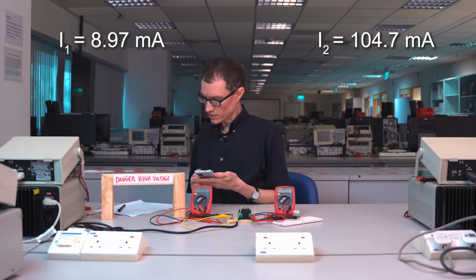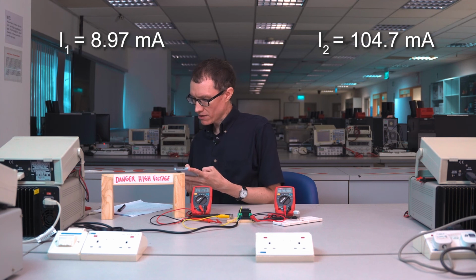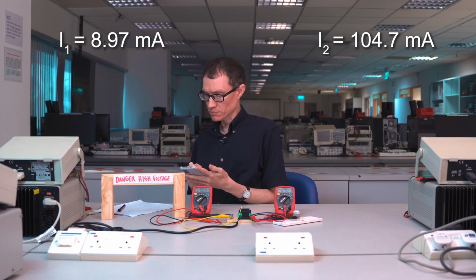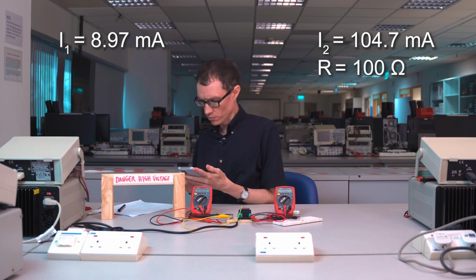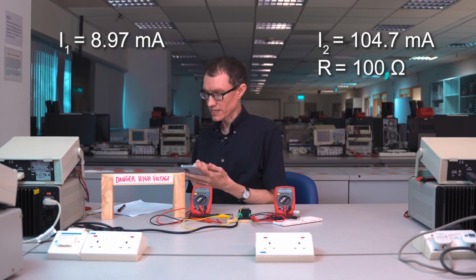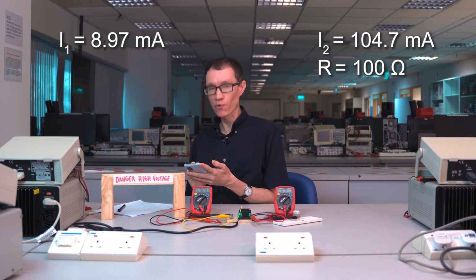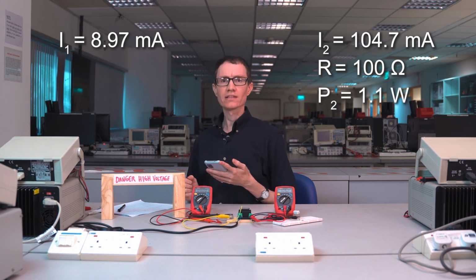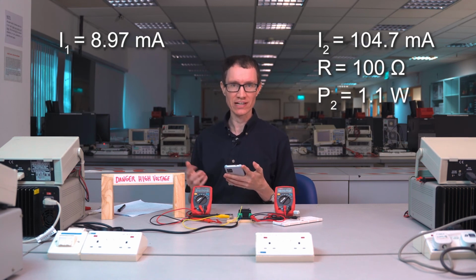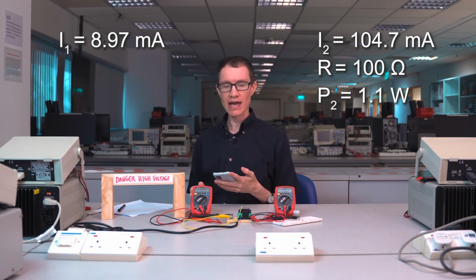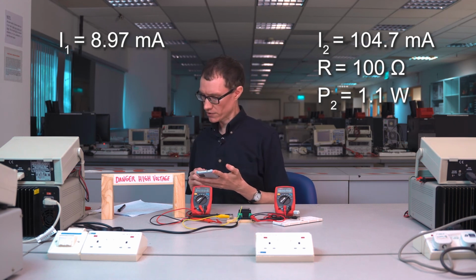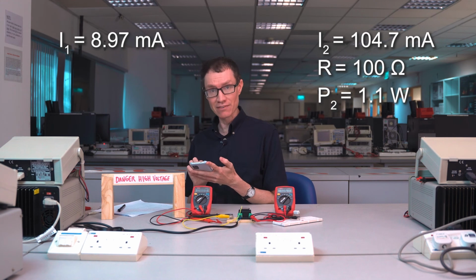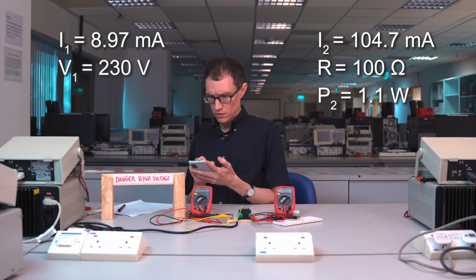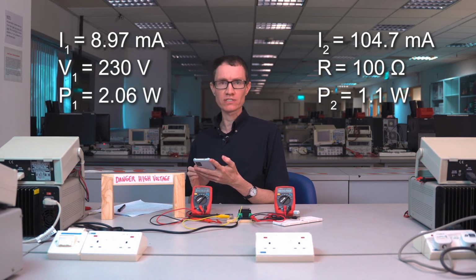Let's start with the secondary side. We have 104.7 milliamps, so taking I squared times R, which is 100 ohms, we find that on the secondary side we're consuming 1.1 watts of power. Now let's see how much power we're putting into the transformer on the primary side. That would be I times V, where the current is 8.97 milliamps and we have 230 volts, which works out to 2.06 watts.